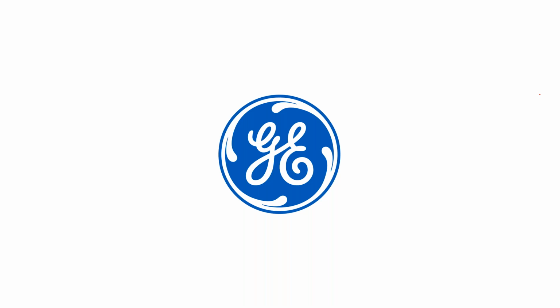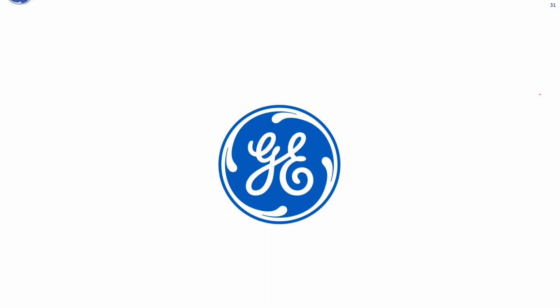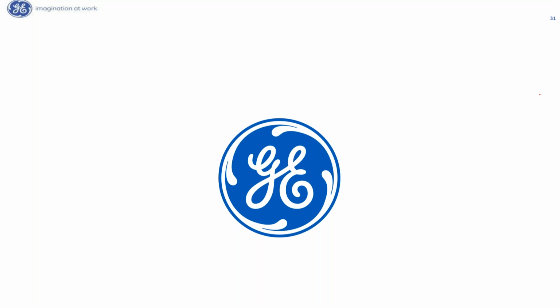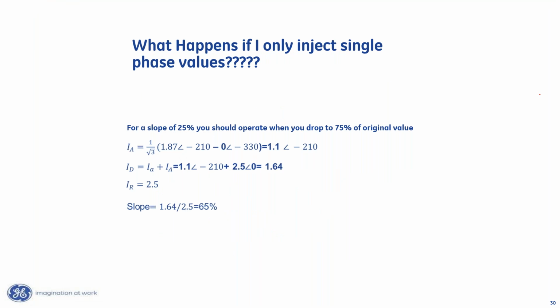So with that said, I am almost out of time. One of the things that I mentioned earlier was that it matters if you're a tester also. The reason it matters if you're a tester is what happens if I inject a single phase quantity. Well, if I inject a single phase quantity, I don't have a B phase to actually compensate my A phase with in the calculations. So I get a very different value.